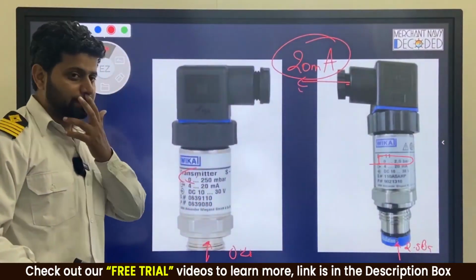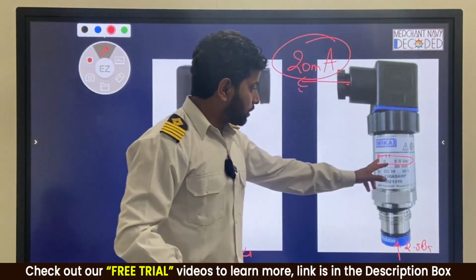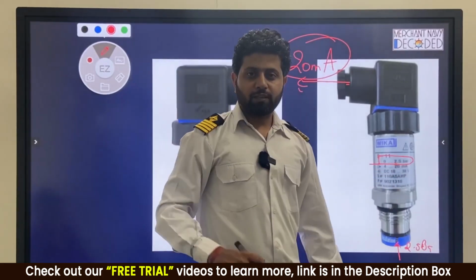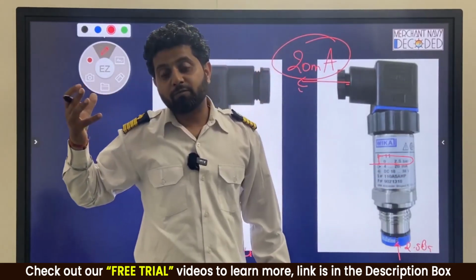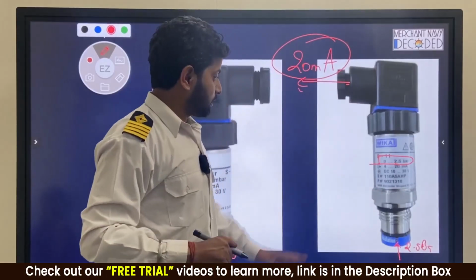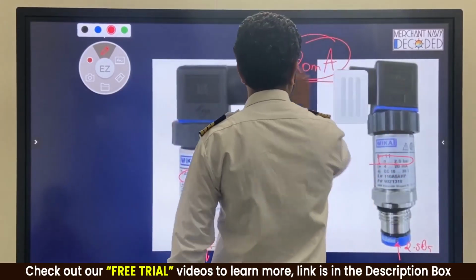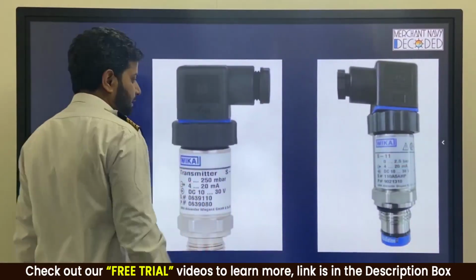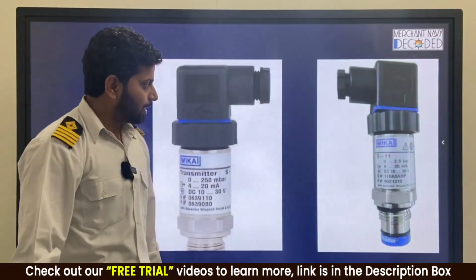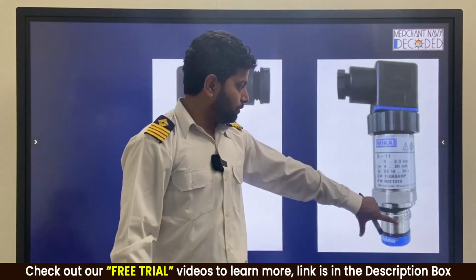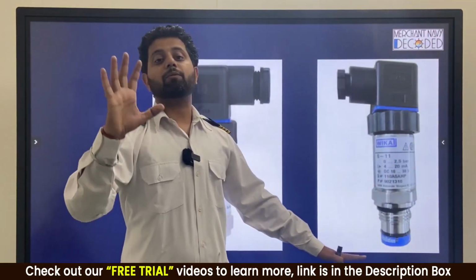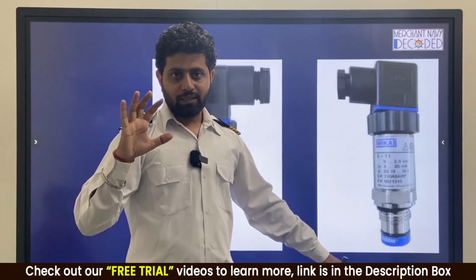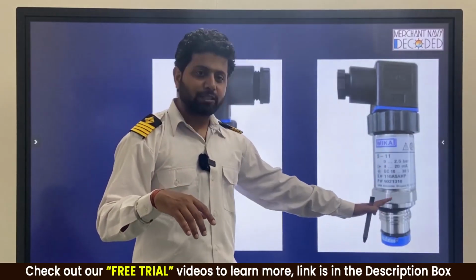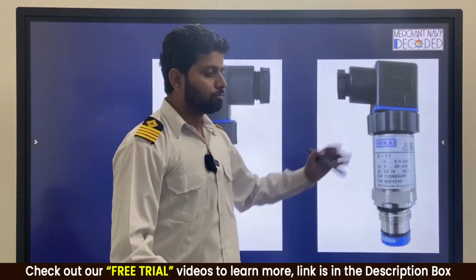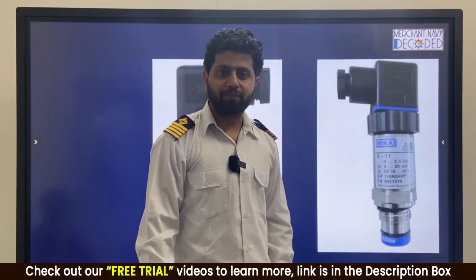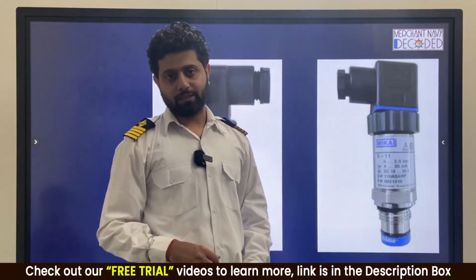When you order a pressure transmitter, you have to see what is the range, what is the output value, whether you want it in milliamps, sometimes it can be in millivolts as well. The company is important, the type of pressure transmitter is important, but the most important thing is range, range, range. Say this is the range of 0 to 2.5 bar. So you will put it in a pipeline where the pressure can go maximum up to 2.5 bar, right? But suppose you put it in a place where the pressure can go up to 5 bar, this won't work because its maximum range is 2.5 bar. इसकी औकात से बाहर जाने की बात कर रहे हैं. That is why. Copied, guys?